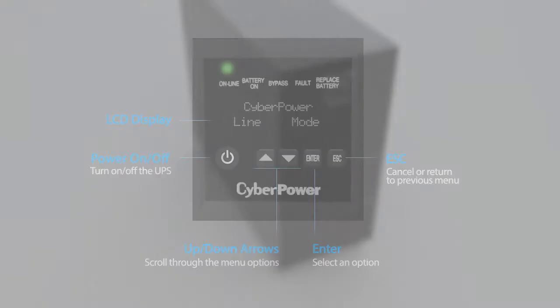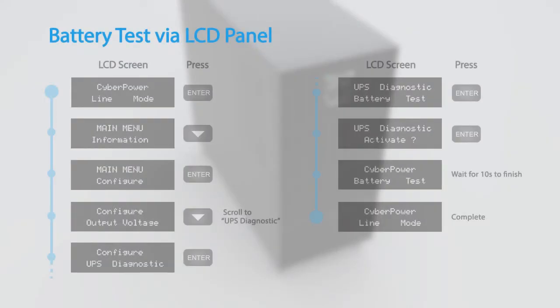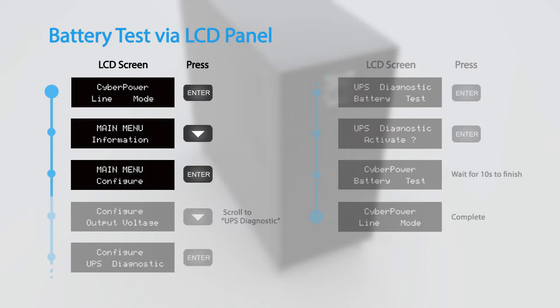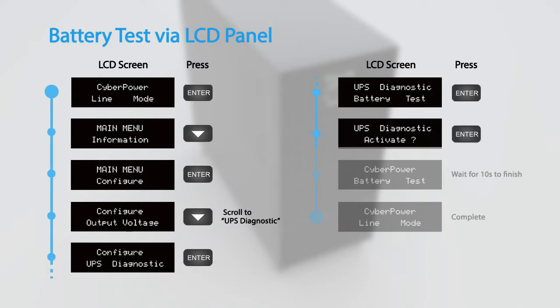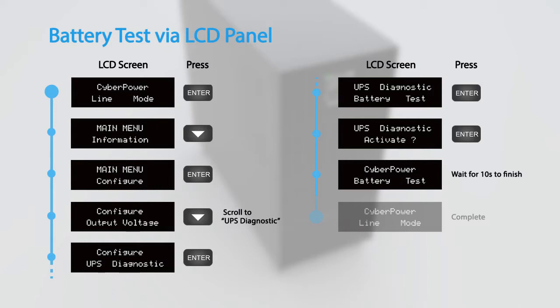To perform battery test via the LCD panel, access the configuration menu and scroll to UPS diagnostic. Select battery test and press enter to activate. The UPS will switch to battery mode for 10 seconds and then return to normal operation.